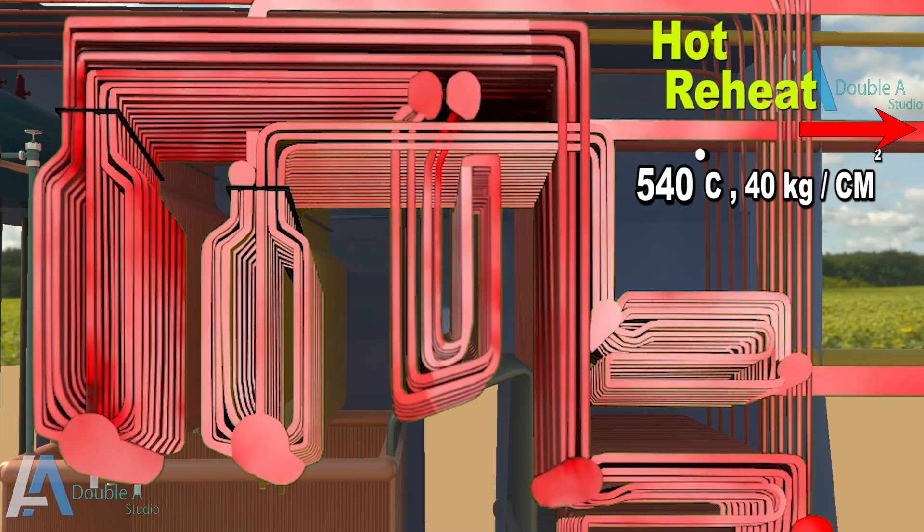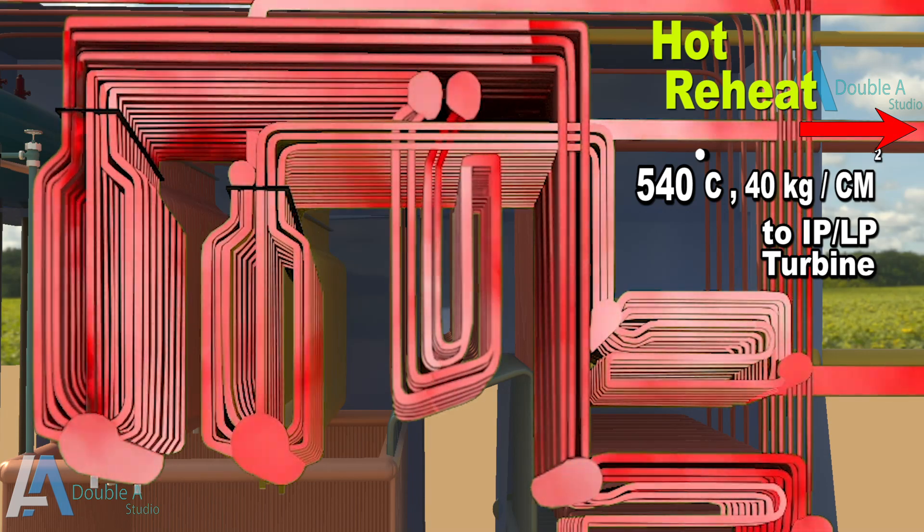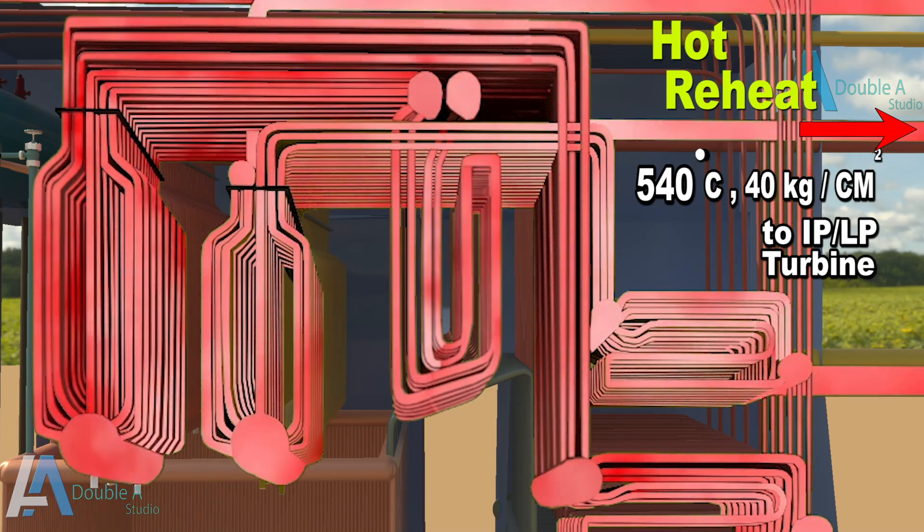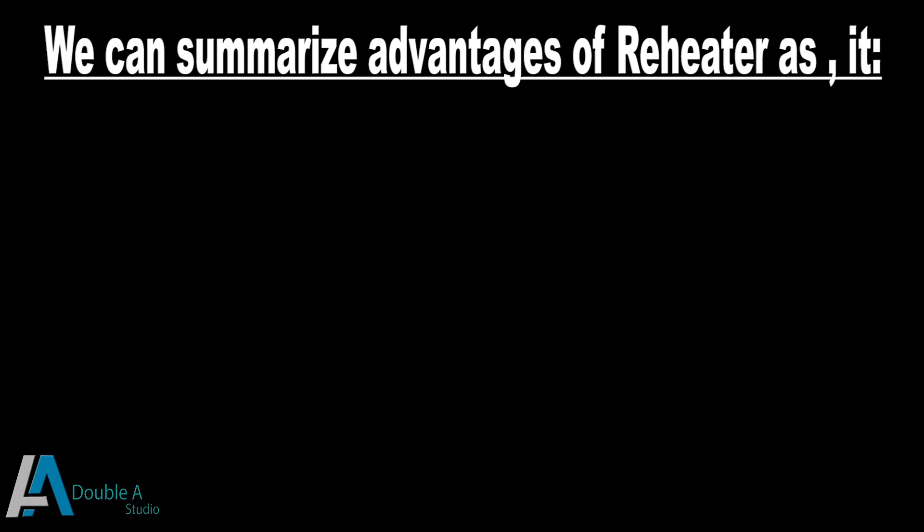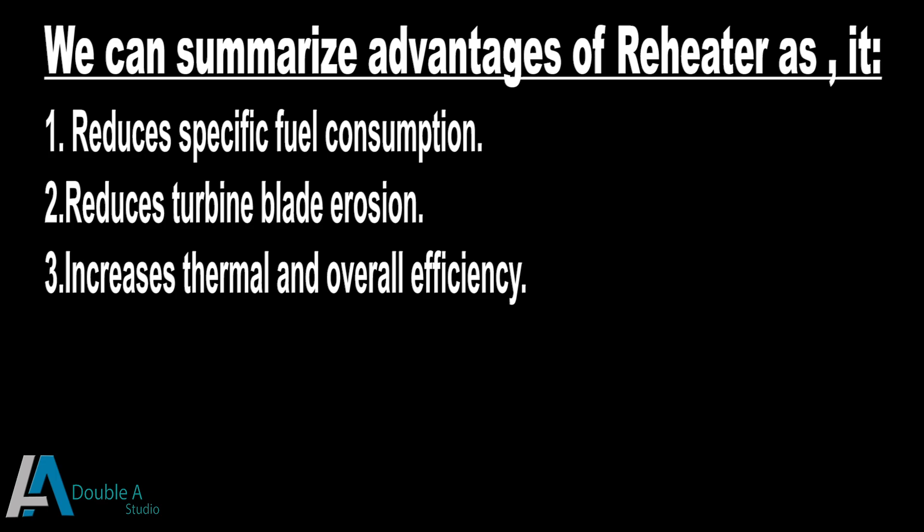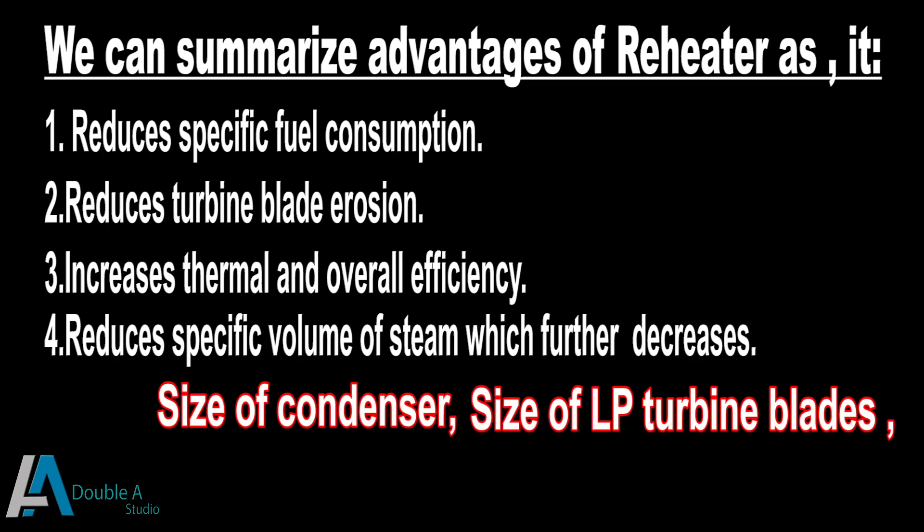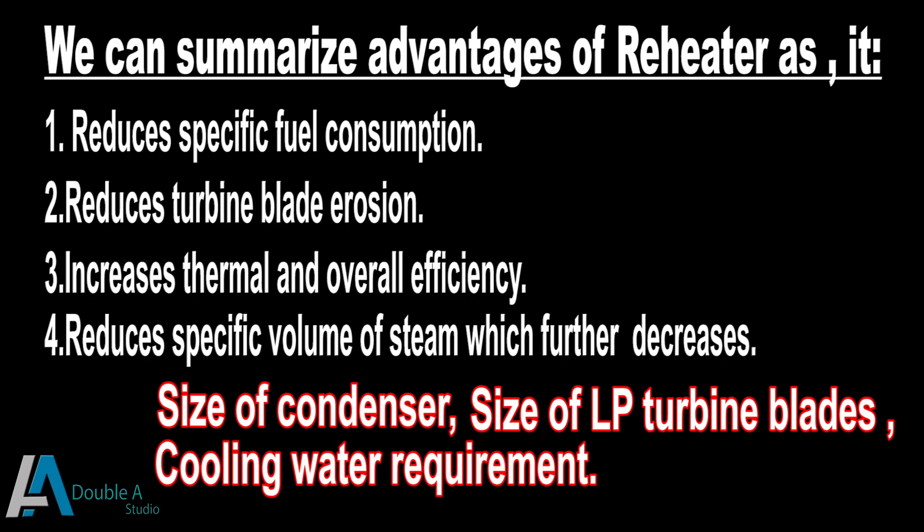From here, hot reheat is sent to IP-LP turbine for further expansion and work. We can summarize advantages of reheat as it reduces specific fuel consumption, it reduces turbine blade erosion, it increases thermal and overall efficiency, it reduces specific volume of steam, which further decreases the size of condenser, the size of LP turbine blades, and also the cooling water requirement.